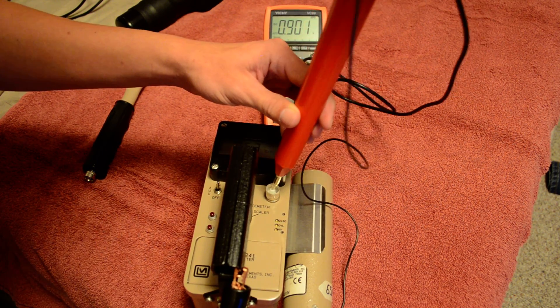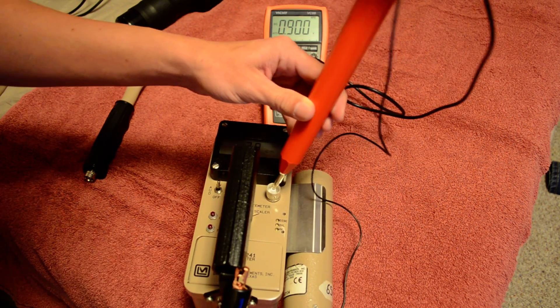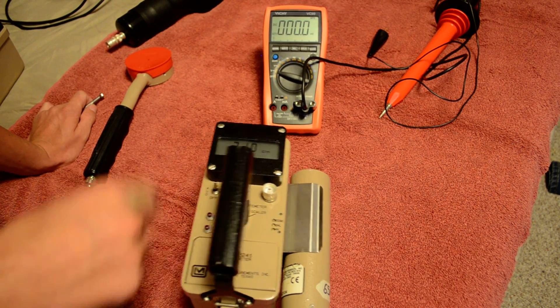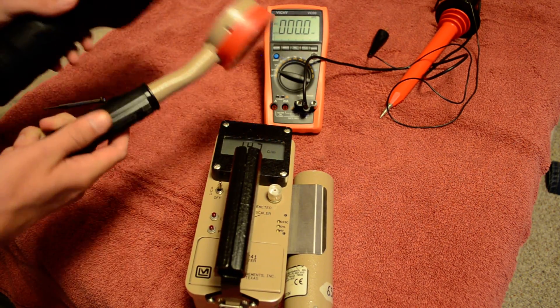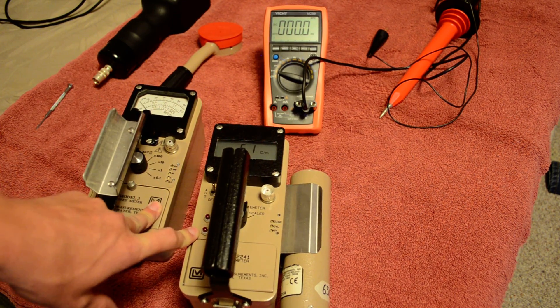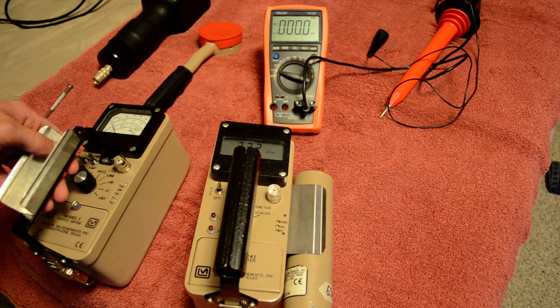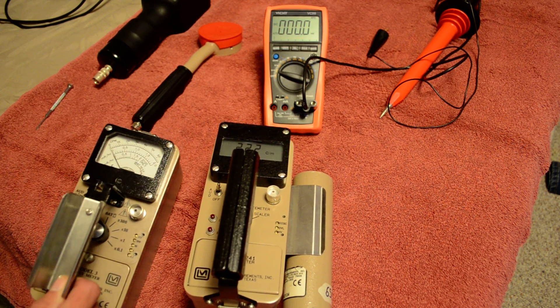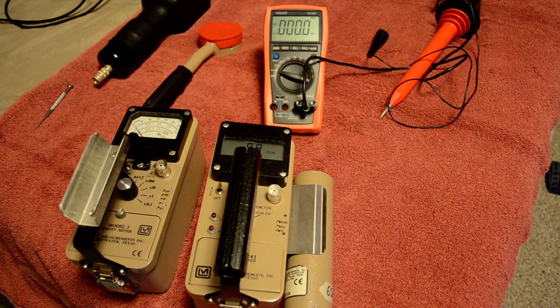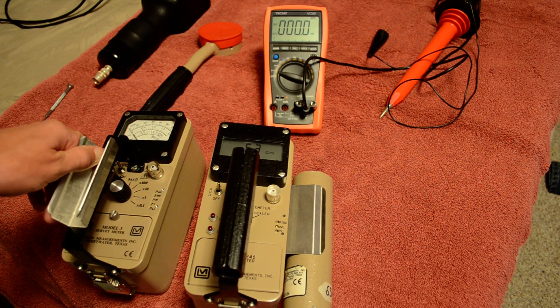That's roughly 900 volts — my OCD needs it exactly 900 volts. Now that we have this set at 900 volts, we can use either the scintillometer or the pancake probe, since both are set for 900. I just use counts per minute for comparison. If you want to use the exposure reading — millirem per hour or similar — switching back and forth can throw it off. But if you're just using counts per minute, you'll be okay.